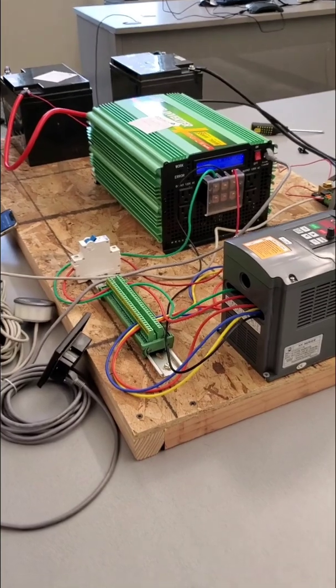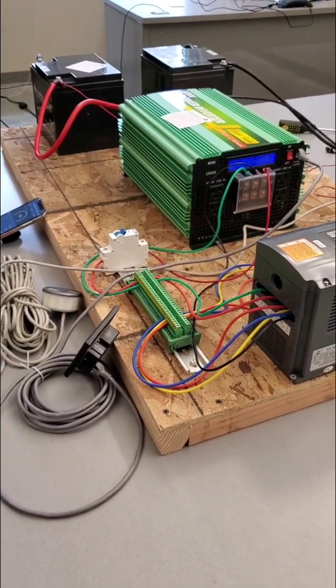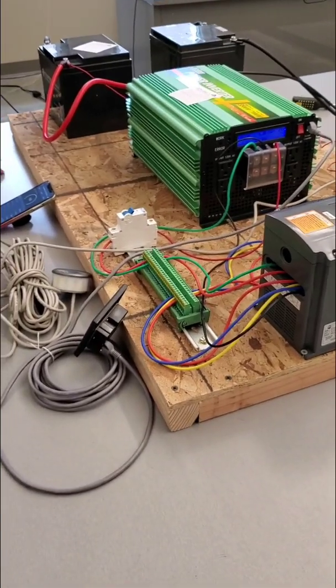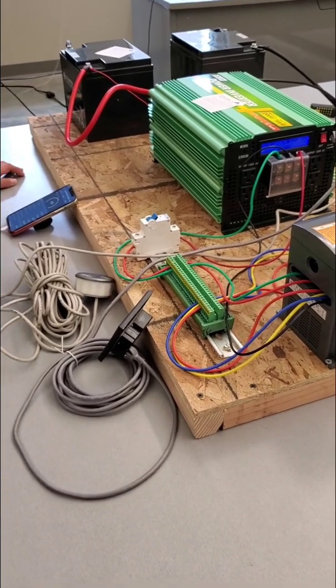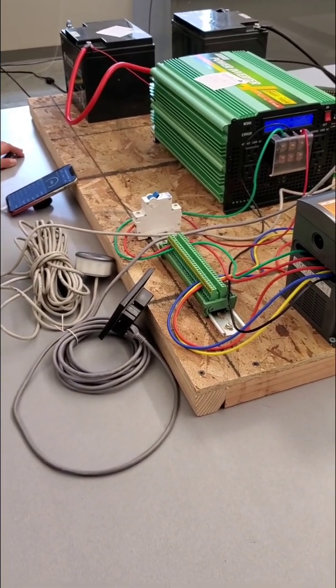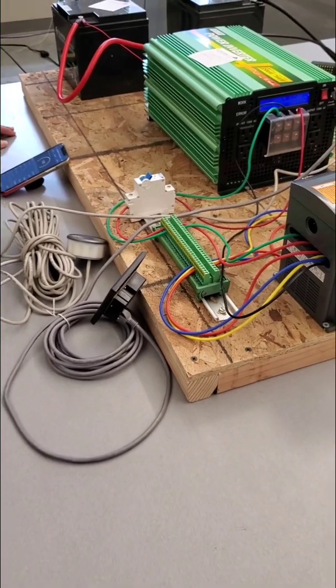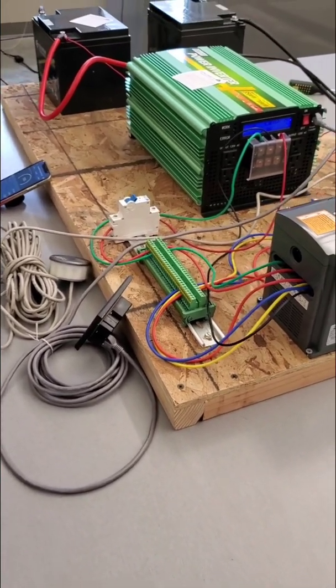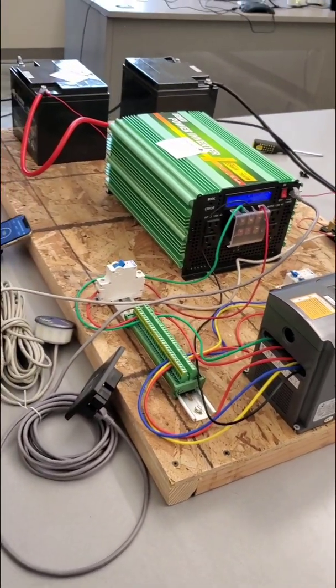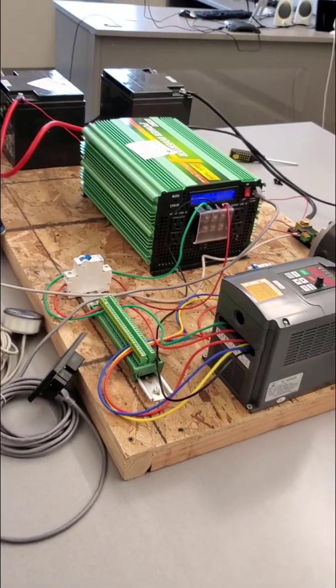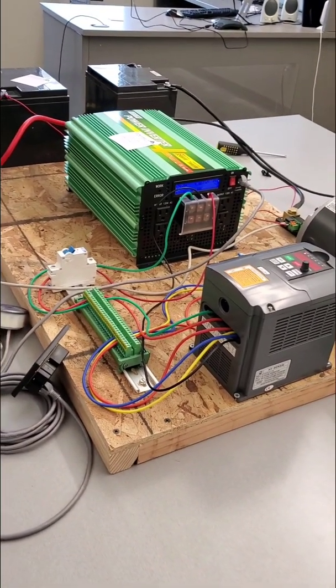So we have several ways of controlling a motor. You can control by using the constant V/F. We call it scalar control. So what we are doing now is called scalar control. We are controlling the frequency and the voltage at the same time. This is the principle of operation.